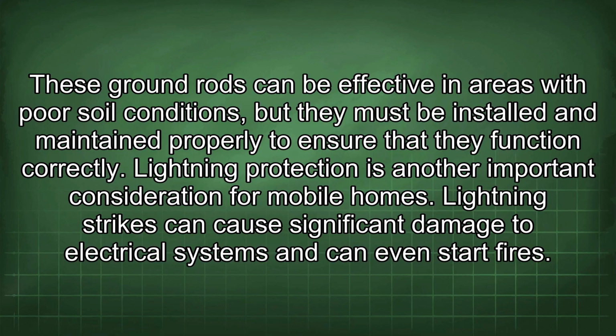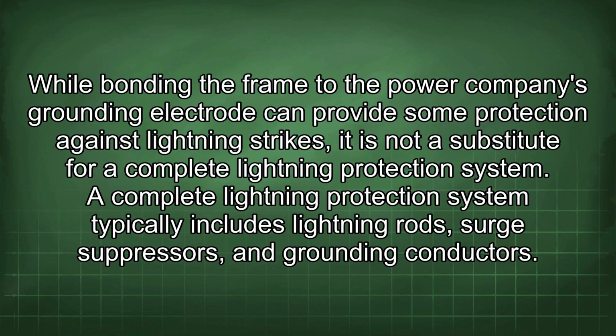Lightning protection is another important consideration for mobile homes. Lightning strikes can cause significant damage to electrical systems and can even start fires. While bonding the frame to the power company's grounding electrode can provide some protection against lightning strikes, it is not a substitute for a complete lightning protection system.